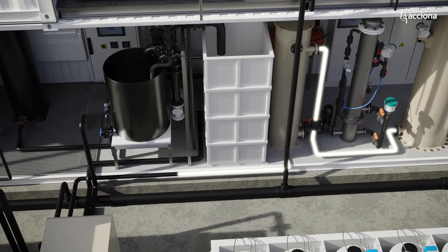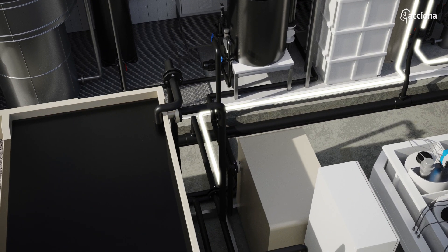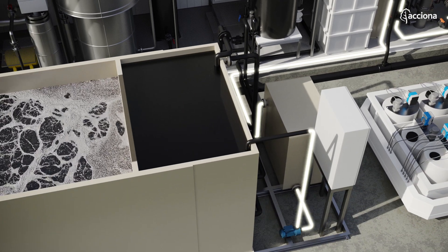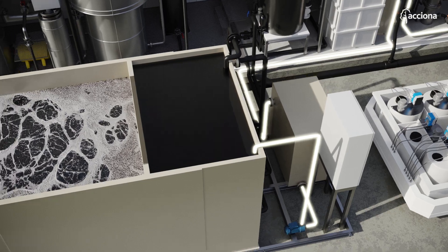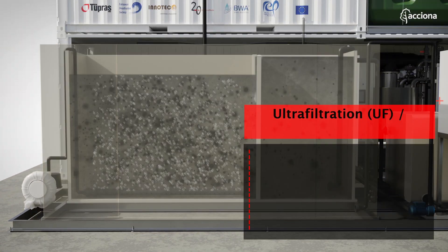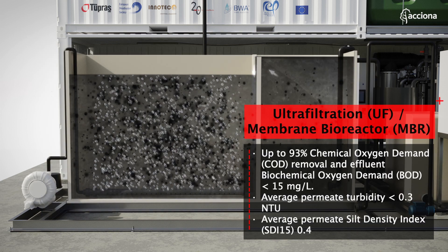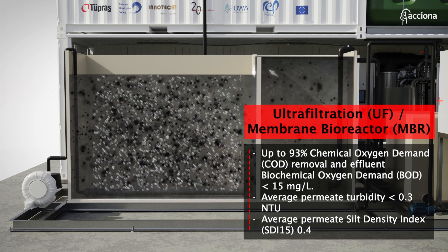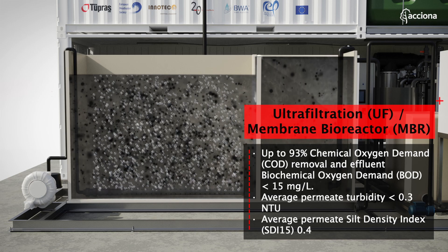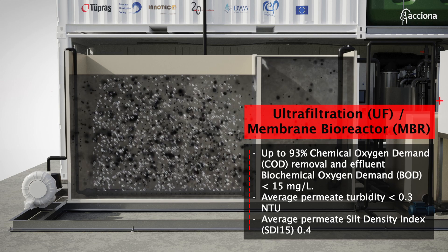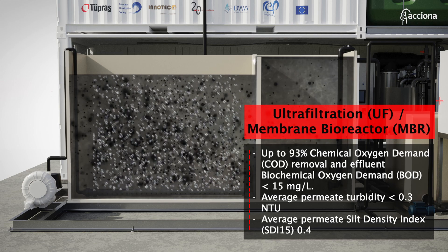Suspended and colloidal matter present in the water are removed by means of ceramic membranes. In the case of refinery wastewater, ceramic membranes are used as part of a membrane bioreactor — the so-called ceramic MBR. In this case, water is firstly introduced in the biological basin where different anoxic and aerobic conditions are maintained, enabling the existence of different microorganisms which degrade the organic matter.